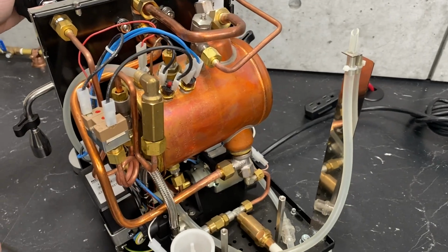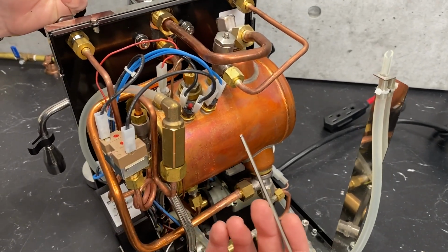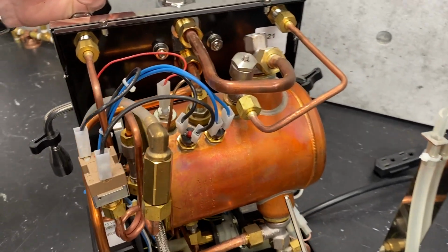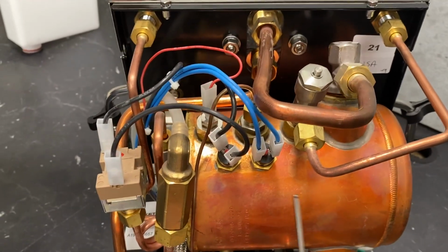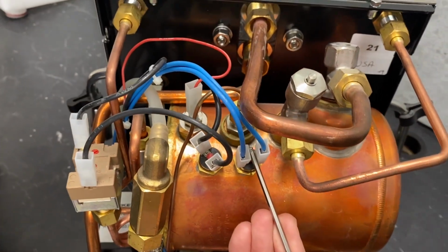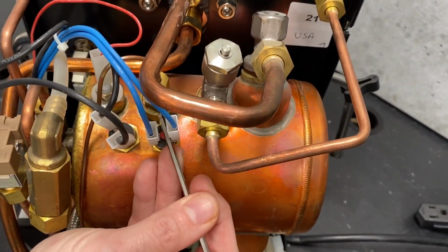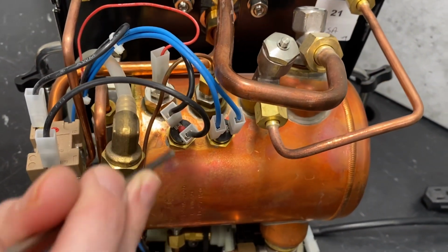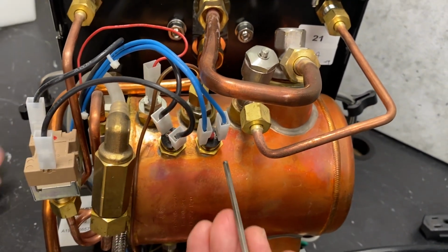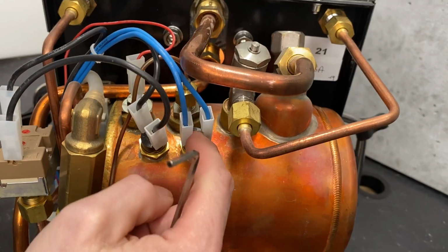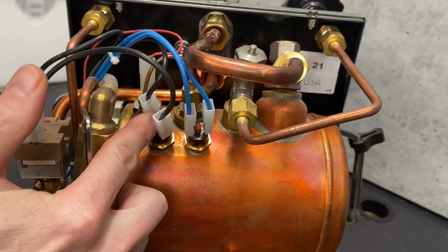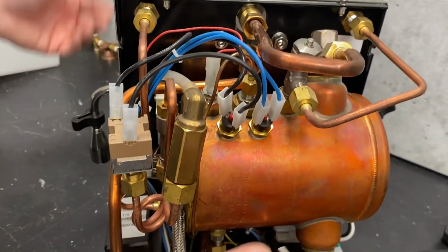So we're going to move on to the top of the boiler here. A couple of the electronic connections you see up here. First of all, you have your high limits. You have one for your neutral and one for your load. If you're ever not heating, a real quick and easy thing to check is see if these are tripped. Simple push, see if it clicks. They're like circuit breakers, they're resettable.